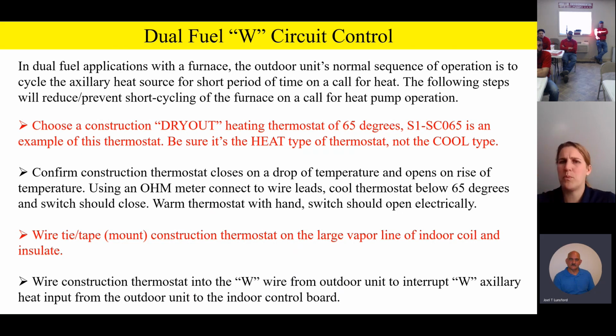basically what I've added to this is if you're going to do dual fuel, the outdoor unit by design generates a W signal every time you go into the heating mode of operation. And it generates that W signal for about 1 minute. What that's for is that if you're hooked up to an air handler, that W signal brings the heat strips on in the heating mode. And what that does is it kind of preheats the air, and it reduces a cold blow condition at the initial start of the heat pump.